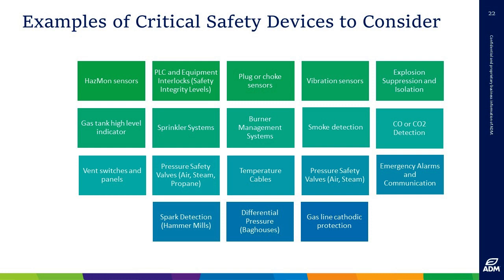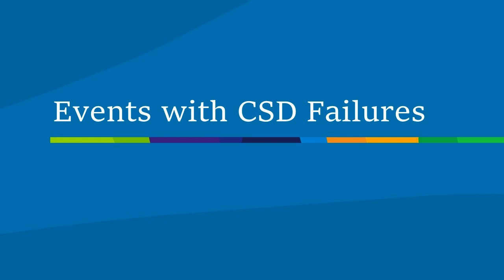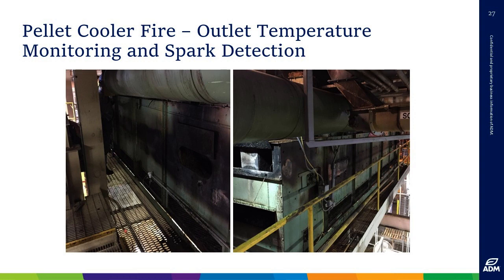So here's just a few events that have happened in our location. I mentioned the pellet cooler and the temperature. The events like this are why we require temperature on exhaust. We've had, maybe it doesn't do it justice, a significant catastrophic pellet cooler fire in a feed plant. The pellets getting too hot, getting stagnant in the cooler, and not checking the outlet temperature, and eventually it results in a big fire.